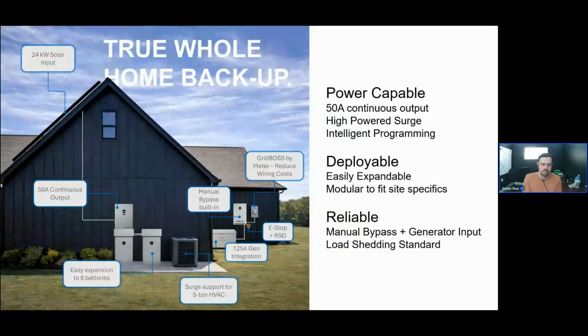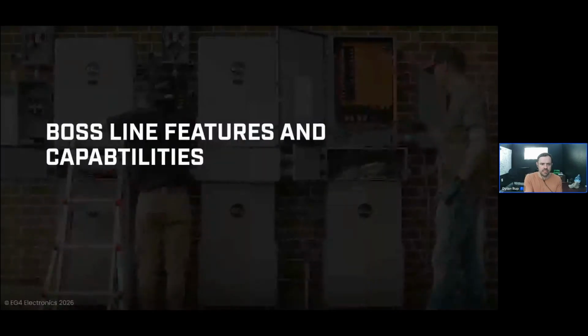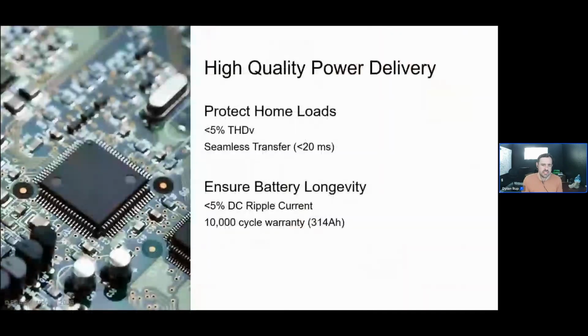Now, getting into some of the more obscure features and capabilities of the system, this unit really is built to deliver incredibly high power quality, both on the AC side of the inverter as well as the DC side of the inverter, which is incredibly important, as we'll talk about in just a moment here. Now, on the AC side of the system, this unit can reliably power even the most sensitive of electronics with little to no issue.